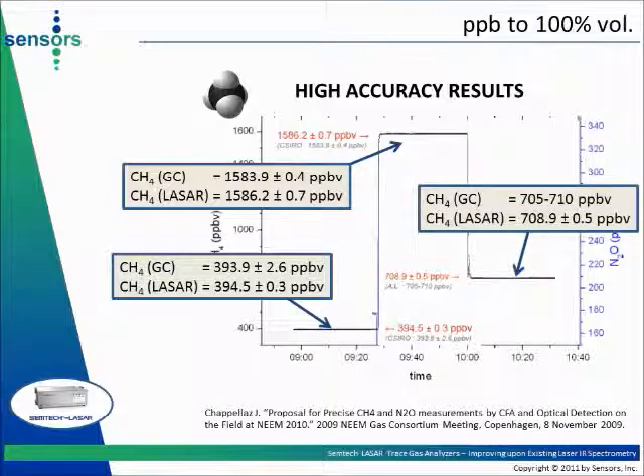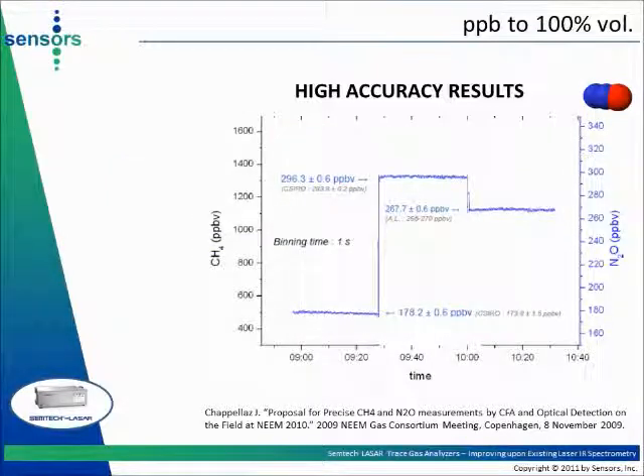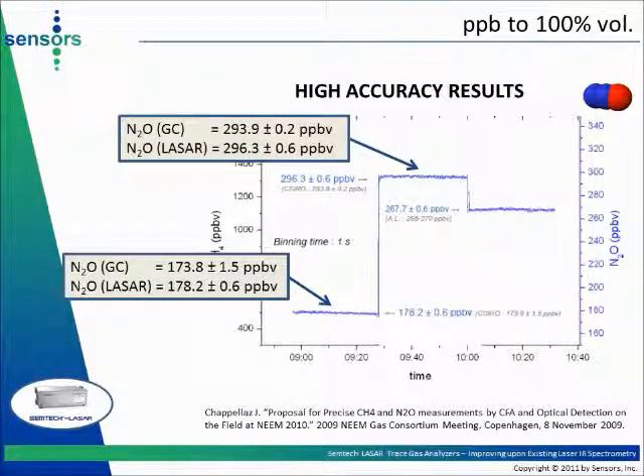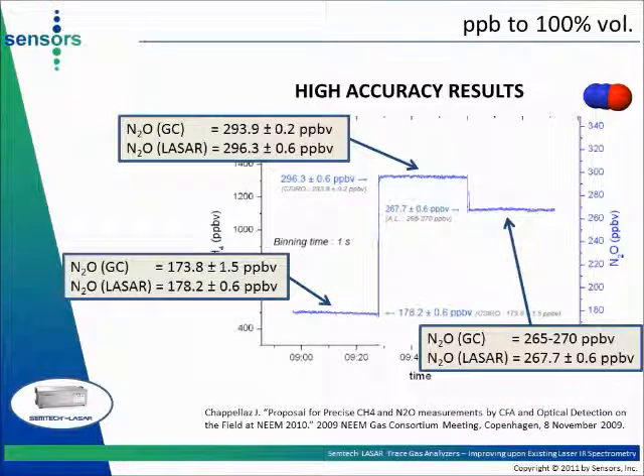For medium levels of methane concentrations, GC measurements ranging from 705 to 710 parts per billion versus 709 parts per billion measured by spectrometry. For nitrous oxide (N2O), Mr. Chapalais reports: for low-level N2O concentrations, about 174 parts per billion by GC versus 178 by spectrometry — a bias error of 4 parts per billion. For high levels, about 294 parts per billion by GC versus 296 — a bias error of 2 parts per billion. For medium levels, GC measurements ranging from 265 to 270 parts per billion versus 268 parts per billion by spectrometry.